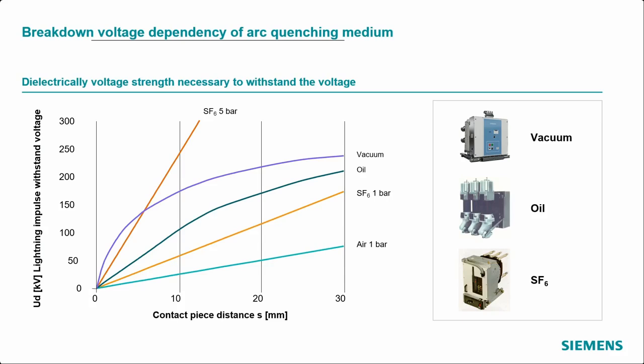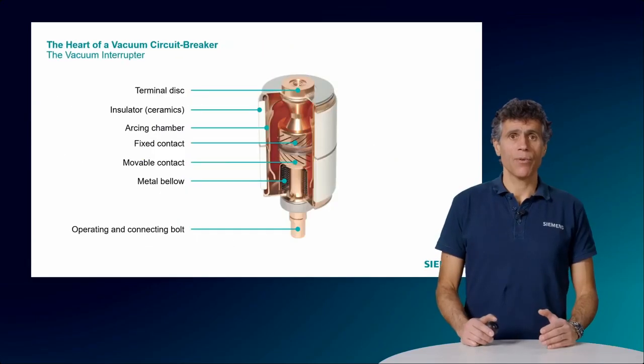Air at very low pressure, called vacuum, is abundant and inexpensive. It has no environmental impact, and it's very effective at higher voltage. The challenge is that vacuum is technically demanding, and maintaining the ideal vacuum conditions is potentially expensive. So here you see a cutout of a vacuum tube.